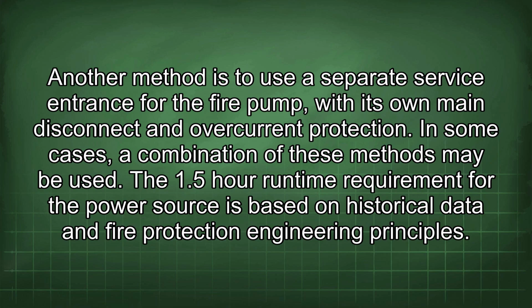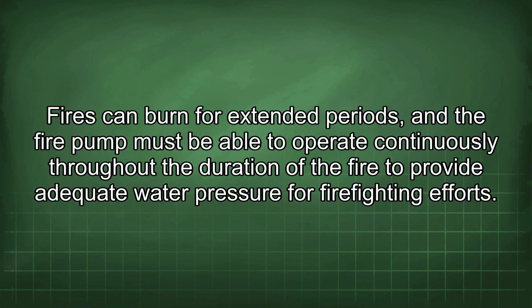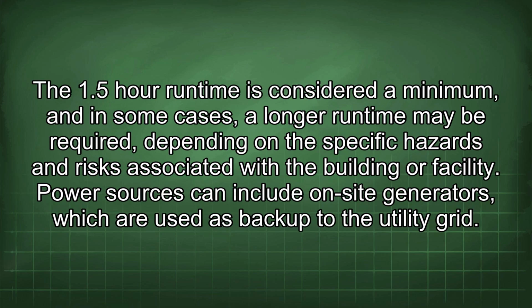The 1.5-hour runtime requirement for the power source is based on historical data and fire protection engineering principles. Fires can burn for extended periods, and the fire pump must be able to operate continuously throughout the duration of the fire to provide adequate water pressure for firefighting efforts. The 1.5-hour runtime is considered a minimum, and in some cases, a longer runtime may be required, depending on the specific hazards and risks associated with the building or facility.